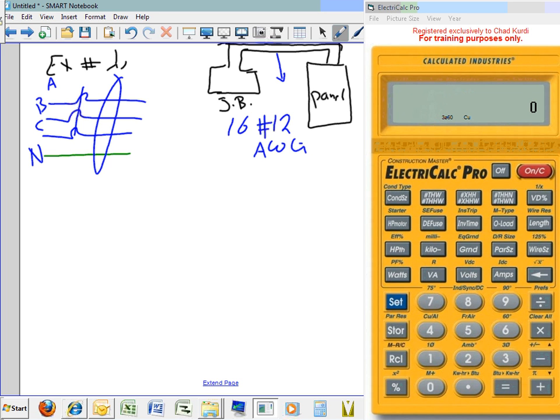AWG. Okay, suppose guys I have a panel like this, and I'm taking a 3/4 of an inch EMT conduit, and I'm pulling 16 conductors number 12 in there. Can I do that fill-wise? Yeah, if you go do the fill calculation, you can.